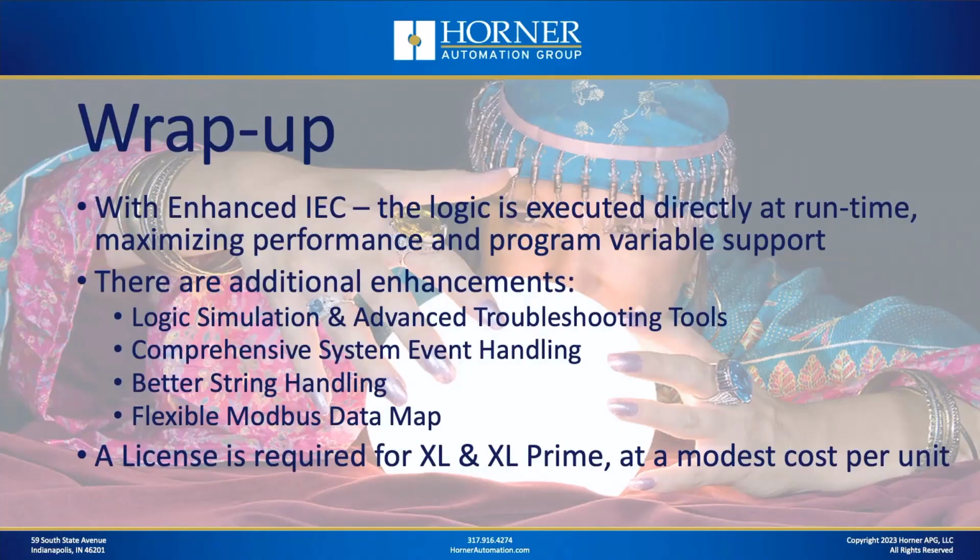Okay, let's go ahead and wrap up our topic for today. So with Enhanced IEC, one difference between Enhanced and Standard IEC is that the logic is directly executed at runtime. No translation required before download, which effectively means we've maximized our performance and the number of program variables that we can support. And we've got additional enhancements as well. The ability to do logic simulation and use some advanced troubleshooting tools like breakpoints and trace points, comprehensive system event handling that can handle, for instance, an issue with an array index that we didn't anticipate, much better string handling capability, and a flexible Modbus data map.